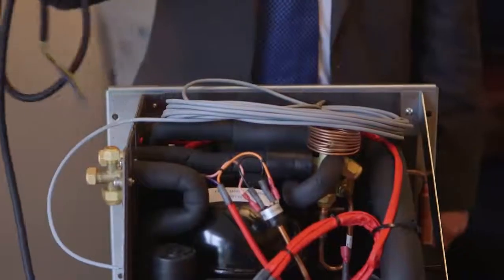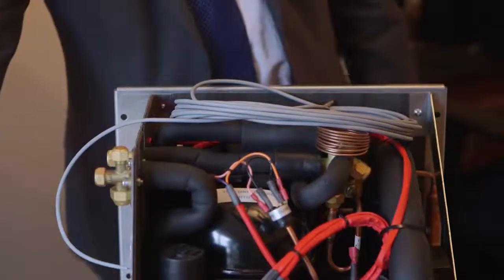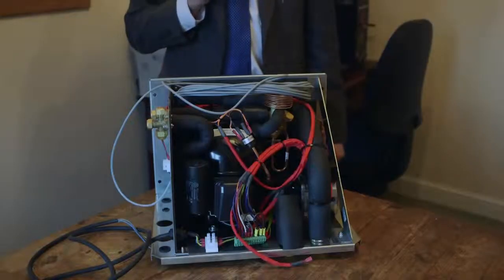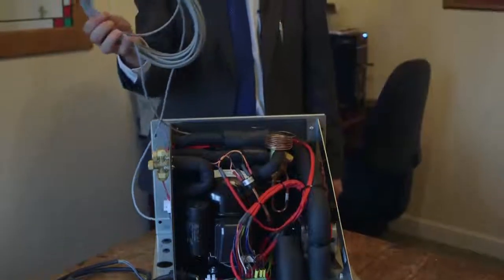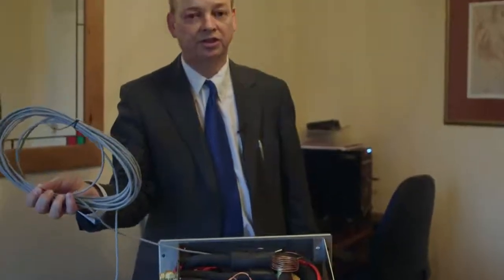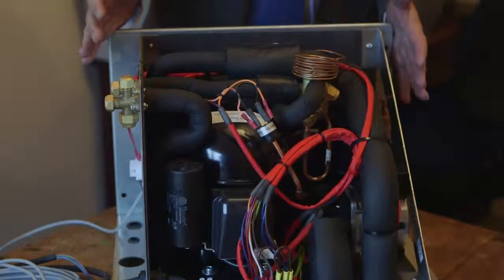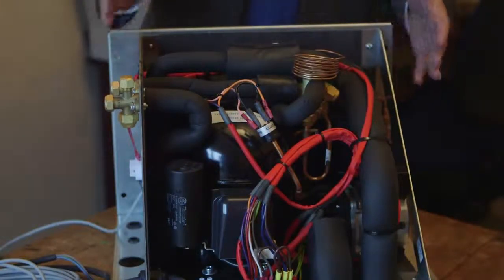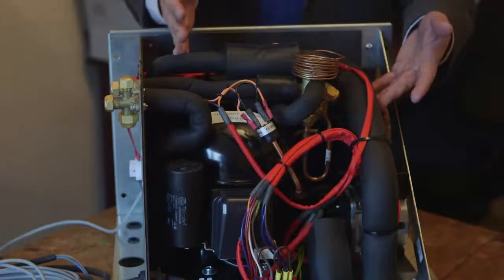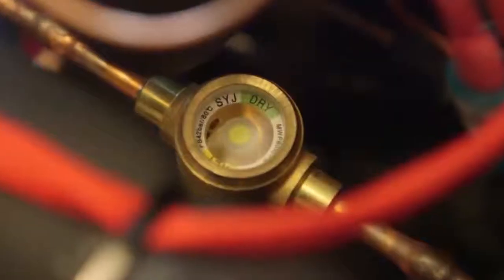The little magic box is connected to the power supply by a fused spur. We have the power cord, and you'll notice that it has a connection in the front, allowing for it to be replaced at any time. We also have a cord which lays up against the side of the cylinder and records the temperature. The box has been designed for ease of maintenance, and everything is insulated to a very high standard. We have the refrigeration connections on the side and a sight glass for the F-gas engineer to diagnose the system.